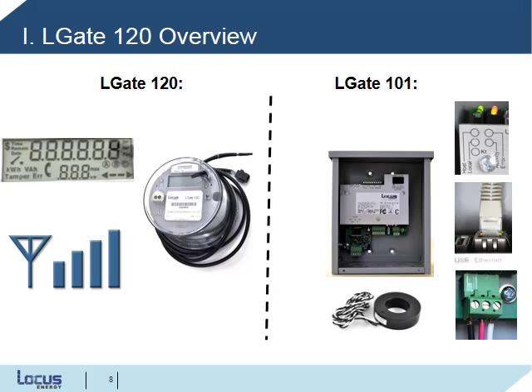Another key difference lies in establishing the data connection. The LGate 101 requires a hardwired Ethernet or Ethernet over powerline connection to the local area network, which in many cases means that the installer must enter the building to access network devices. The cellular-enabled LGate 120 with Ethernet backup provides multiple options for establishing a data connection. As for site commissioning, the LCD screen on the LGate 120 is extremely easy to read, and it provides far more information than the LED indicator lights on the LGate 101.